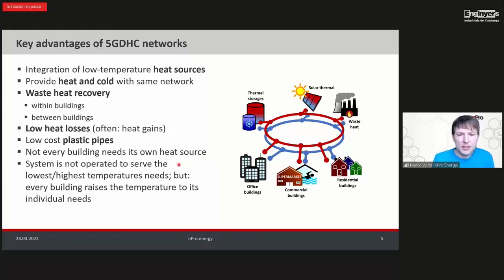And then one of the advantages is that this network allows the buildings to actually take the temperature that it actually needs. So if we imagine a district with many different buildings, like modern buildings, which need a low temperature, and also old buildings, which may need a higher temperature for heating, then this network allows that we just distribute this low temperature to every building, and the heat pumps inside the buildings increase the temperature to the level that the building actually needs.